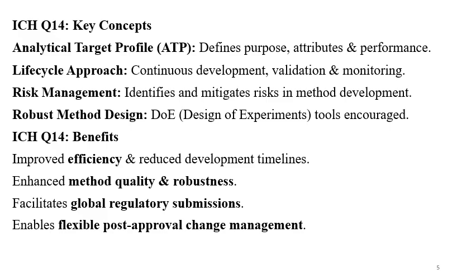The key concepts of ICH Q14 include: first, ATP — the Analytical Target Profile — which defines the purpose, attributes, and performance of the analytical method. Second, a lifecycle approach covering continuous development, validation, and monitoring. Third, risk management to identify and mitigate risks in method development. Fourth, robust method design using tools like DOE — Design of Experiments.